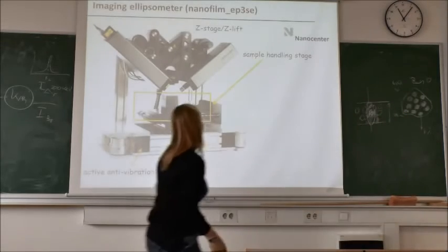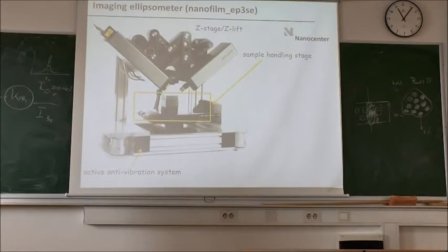Okay, here is a picture of our imaging ellipsometer. This device was funded by the Center of Excellence in Nanoscience and Nanotechnology, and to my knowledge, this is the only imaging ellipsometer in Slovenia. This device consists of a sample handling stage, Z stage, and active anti-vibration system.